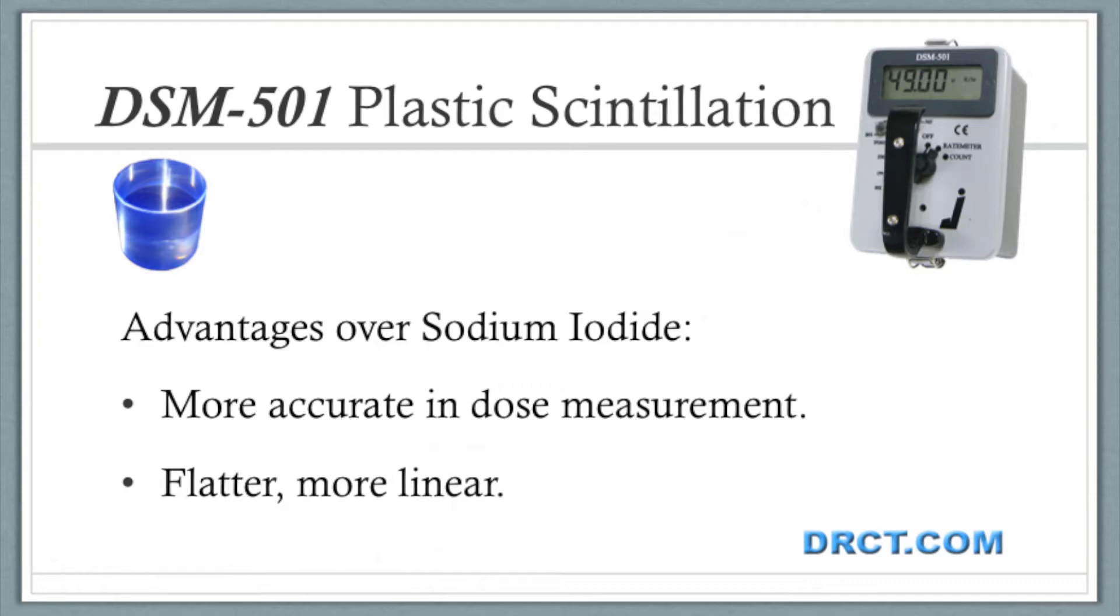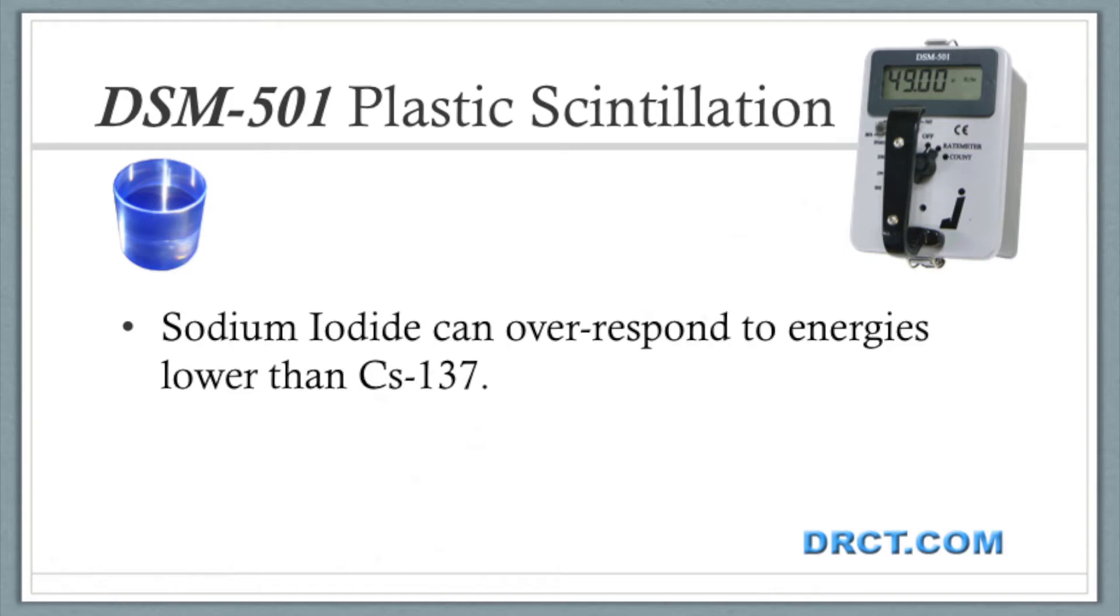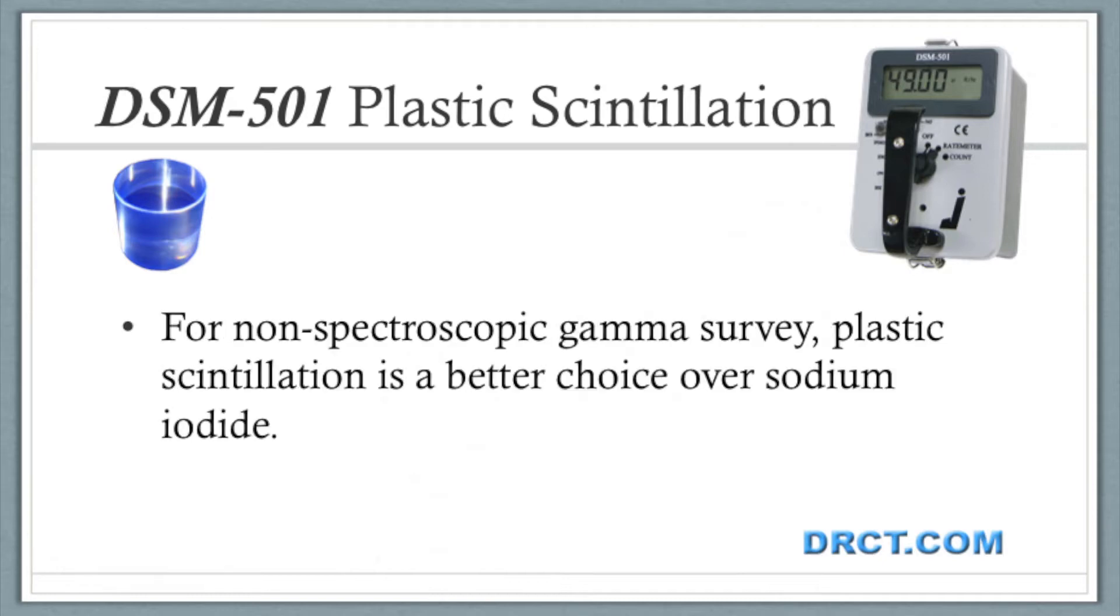It is more accurate in approximating actual dose than an inorganic crystal like sodium iodide or cesium iodide. Plastic yields a more linear, flatter energy response than sodium iodide. The sodium iodide detector can over-respond with energies lower than cesium-137. For non-spectroscopic gamma detection work, plastic scintillation is a better choice than inorganic scintillation.